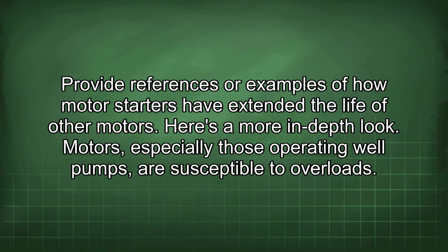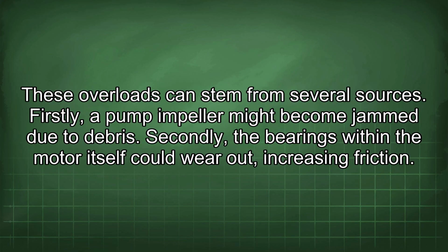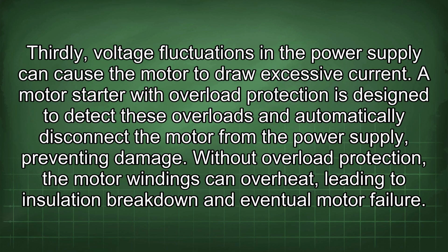Motors, especially those operating well pumps, are susceptible to overloads. These overloads can stem from several sources. Firstly, a pump impeller might become jammed due to debris. Secondly, the bearings within the motor itself could wear out, increasing friction. Thirdly, voltage fluctuations in the power supply can cause the motor to draw excessive current.